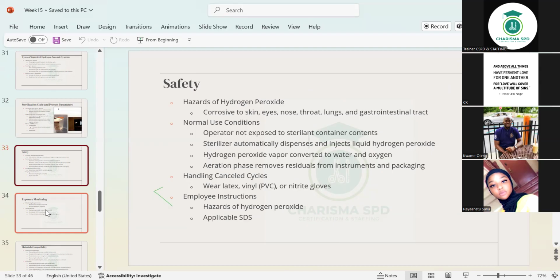But remember, these are all engineering efforts that we've made to this point, such that we personnel don't get exposed to these things. All right. So under normal conditions, you are not exposed to the sterilant if everything works right. The sterilizer automatically dispenses and injects the liquid hydrogen peroxide. The hydrogen peroxide vapor is converted to water and oxygen at the end. The aeration phase removes residuals from the instruments, so we don't have to even worry too much.